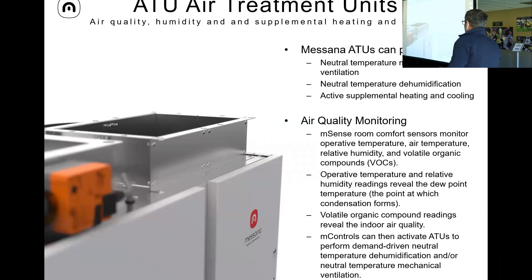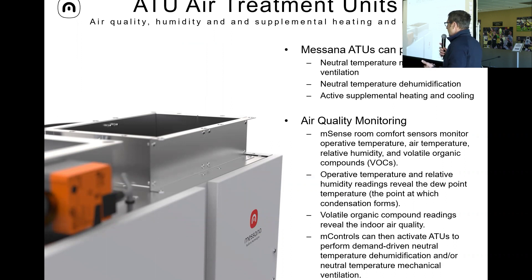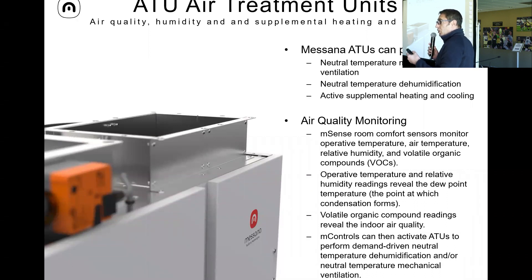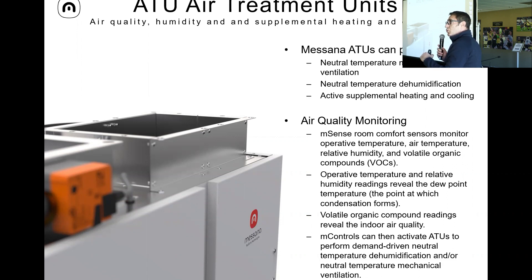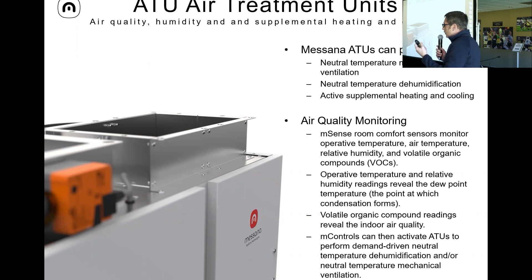The last ingredient in the radiant cooling recipe is controlling the air — specifically, controlling the humidity. Not just to prevent condensation, because that's handled by the control system, but if humidity is elevated we cannot drop the temperature of the ceiling. We can activate the dehumidification system to drop the dew point temperature, which allows us to drop the temperature in the panel, getting more BTU from the panel and using it more versus the fan coil. So we developed an ATU — an air treatment unit — that integrates with our control.